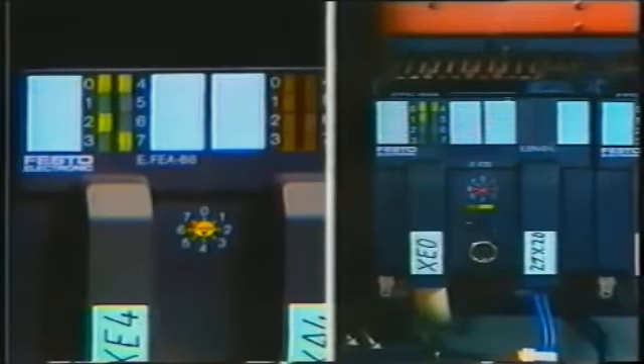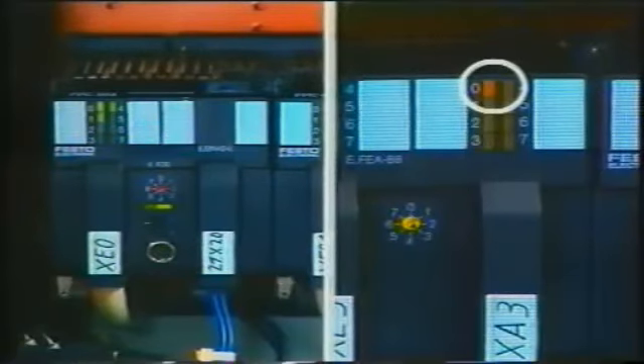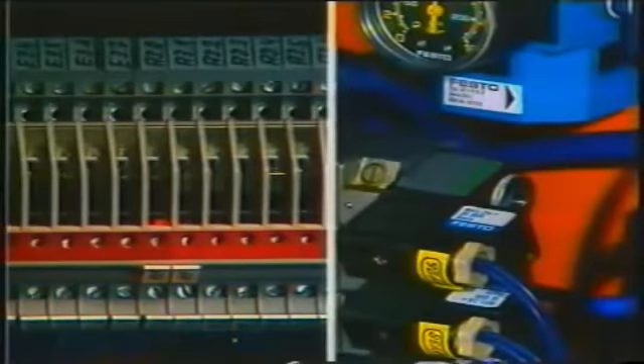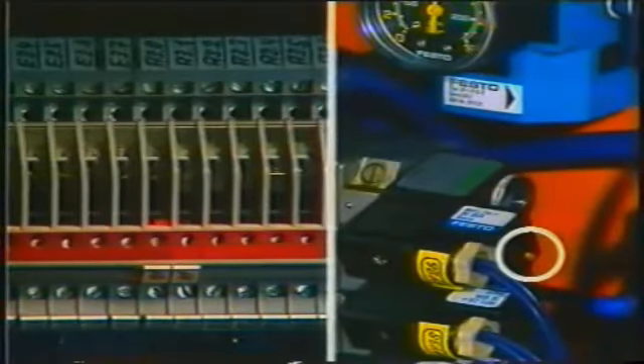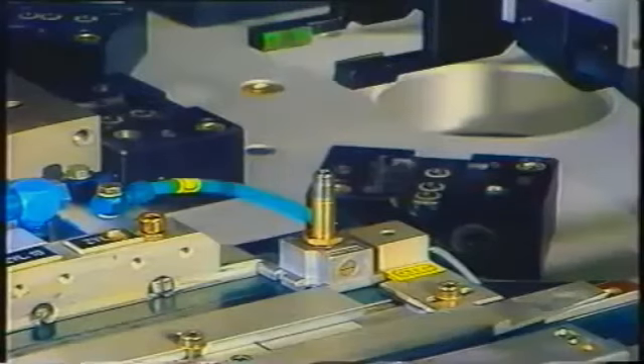In the central control unit, the signal is processed by a stored program, and an output signal results, which is passed to the output module. There it is amplified and conditioned, and then passed via a terminal to the solenoid valve. This switches and causes the cylinder to extend, so that the gripper can pick the valve from the conveyor belt.